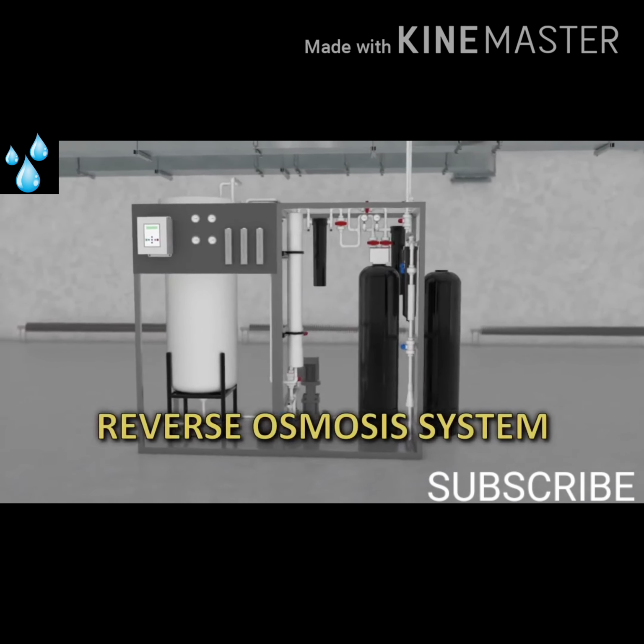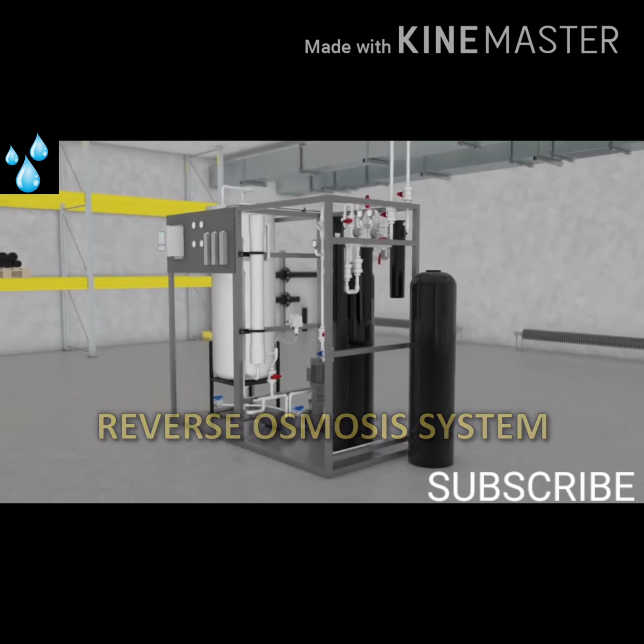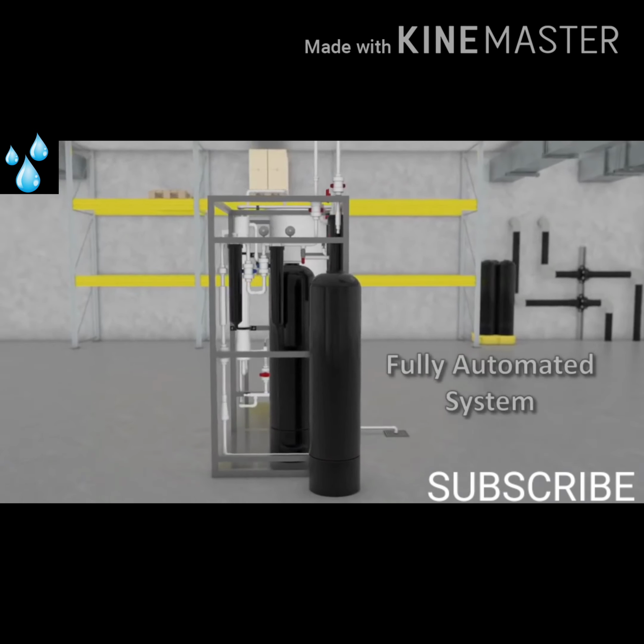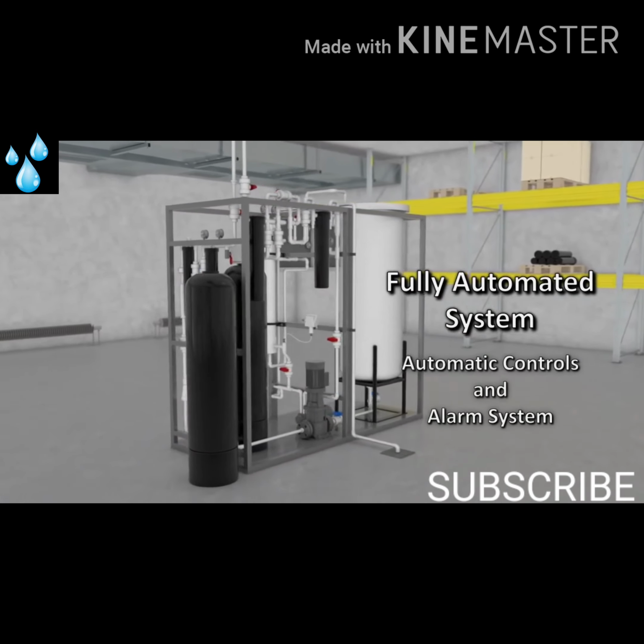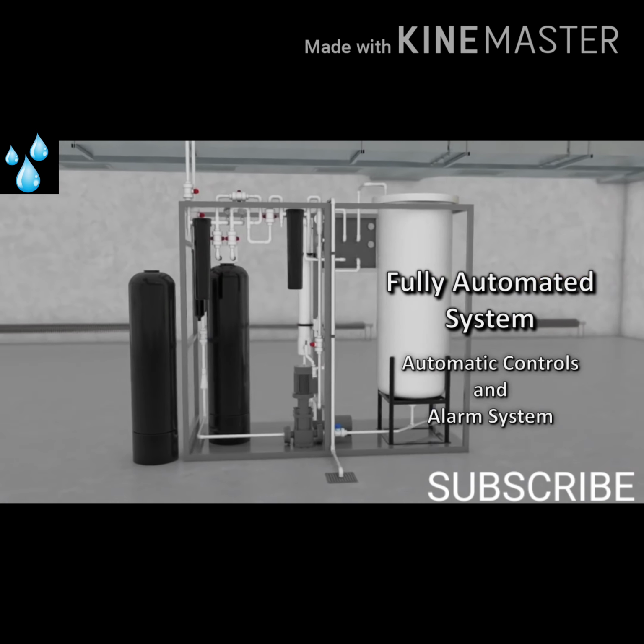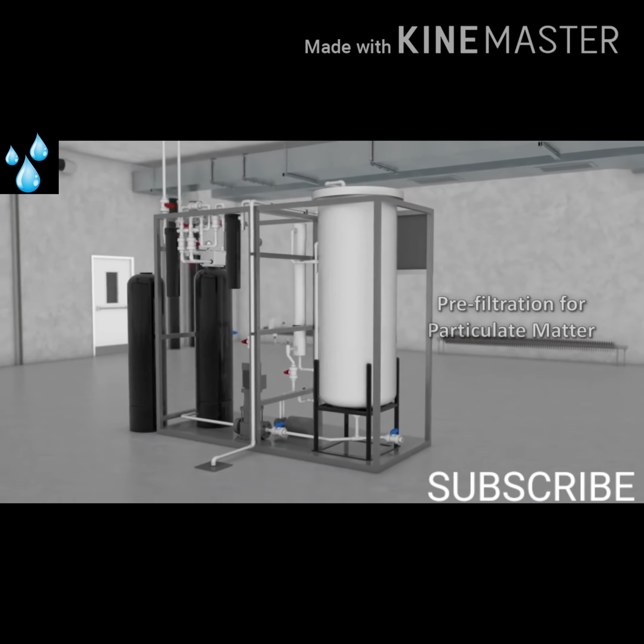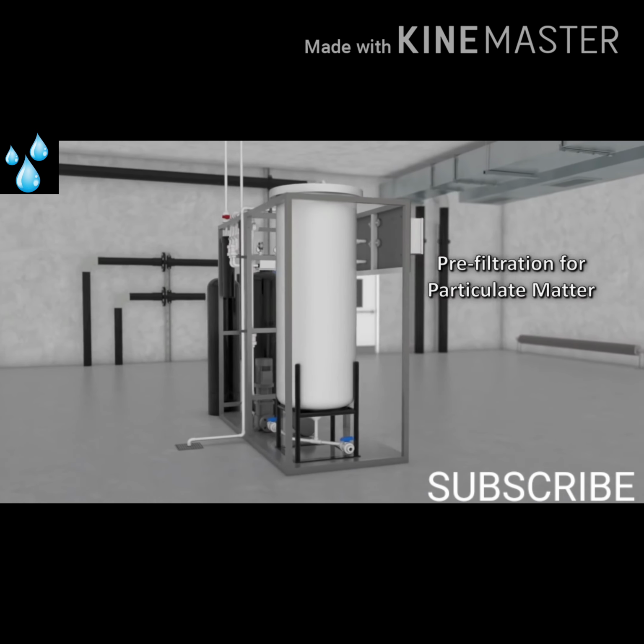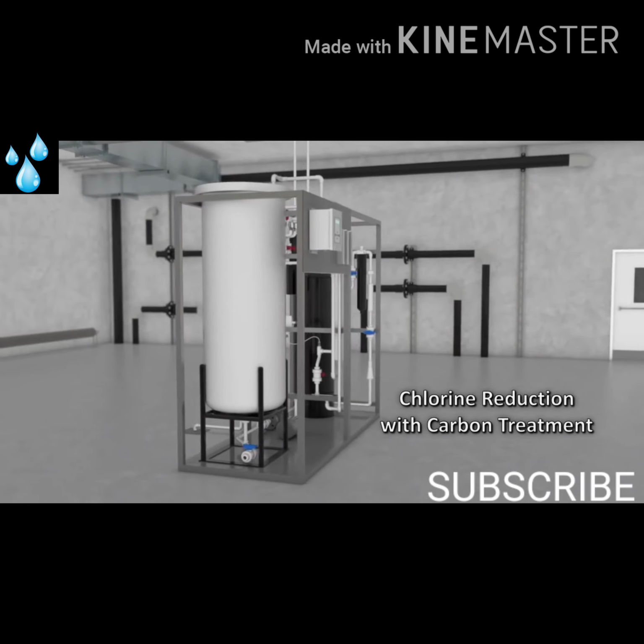This is the high purity reverse osmosis system. Commonly called the RO, it is a fully automated process with automatic controls and alarm system. An RO water system includes pre-filtration for particulate matter and chlorine reduction with carbon treatment.